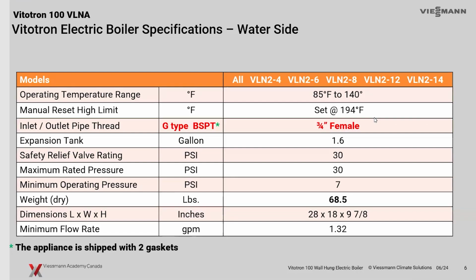The connections are 3/4 inch on the bottom. We'll have a quick review of that. And it does actually come with its own built-in expansion tank, so that's one of those extra components that we will not have to purchase from the wholesaler. However, it's a 1.6 gallon tank. Again, with low temperature, even with a radiant system, your expansion rates could be very limited with the temperature rise that we're talking about.